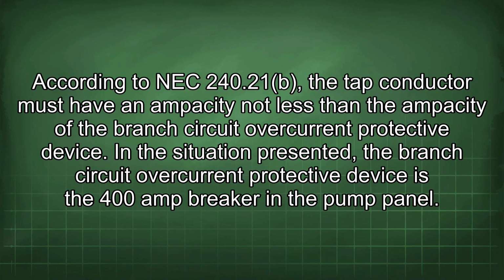According to NEC 240.21, the tap conductor must have an ampacity not less than the ampacity of the branch circuit overcurrent protective device. In the situation presented, the branch circuit overcurrent protective device is the 400 amp breaker in the pump panel.